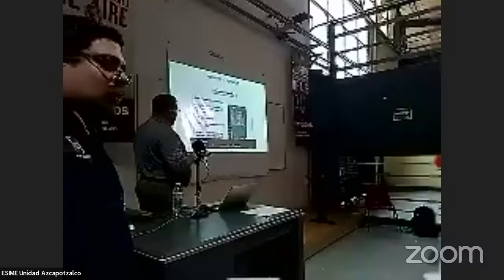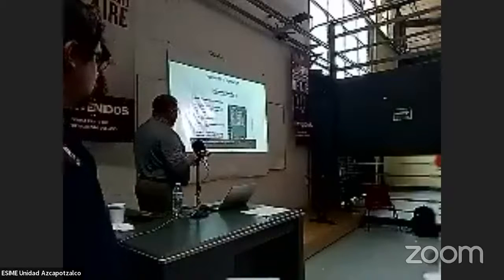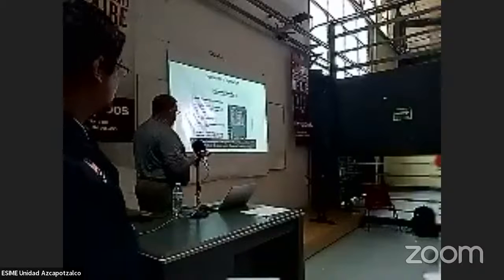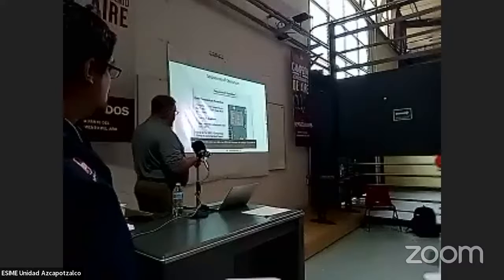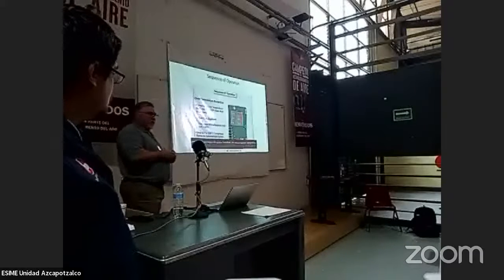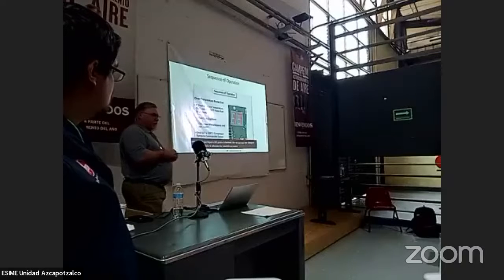Over temperature protection. So remember we talked about the discharge line getting above 225 degrees for 30 seconds. We'll give you the fault code. So it'll show up as a fault code 17. Compressor RPM is reduced until it gets to 200 degrees Fahrenheit. Once it goes below that, it'll ramp back up to the command speed. If it doesn't, then we'll shut the system down with a fault code.